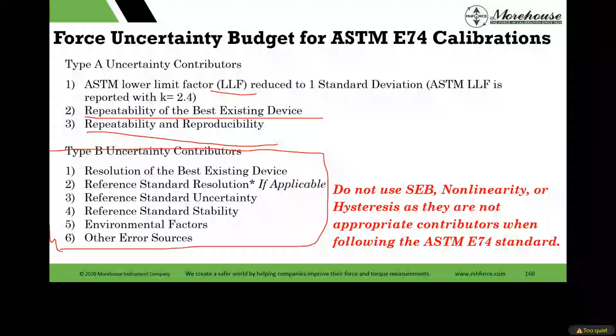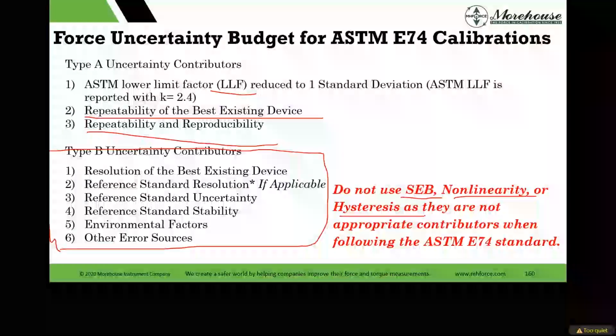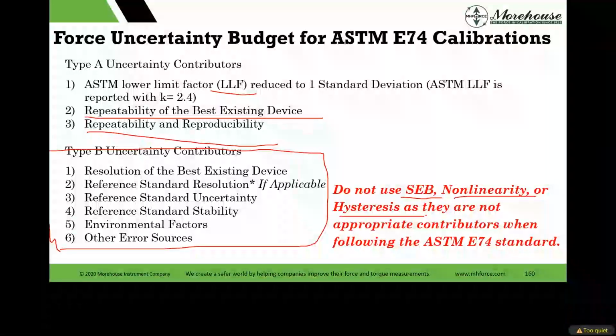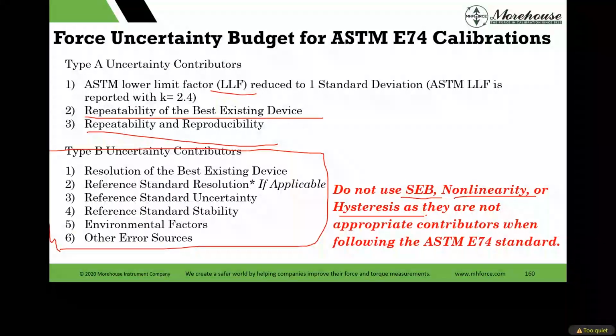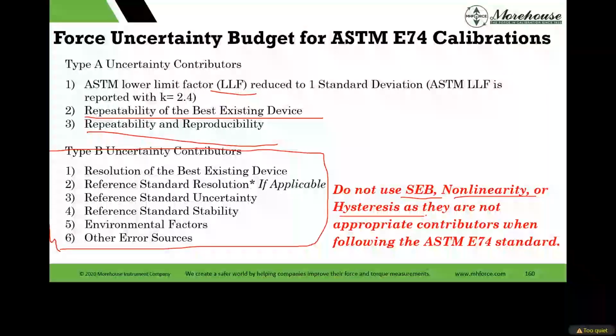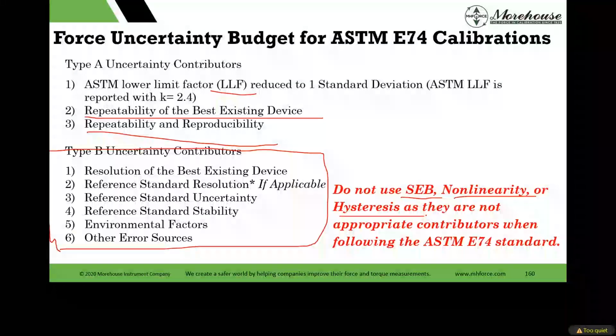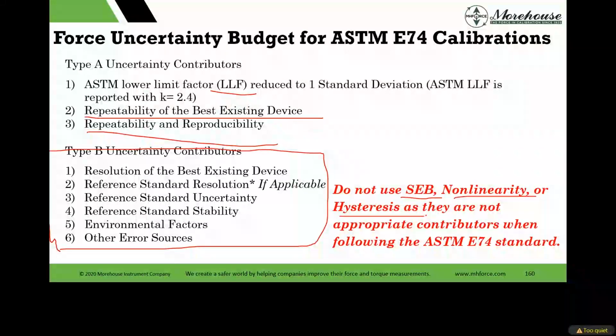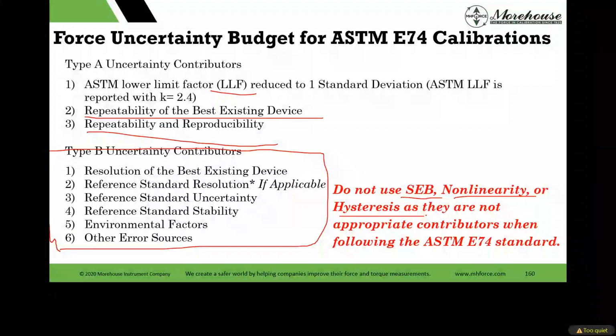What we see people mistakenly do is go back to that spec sheet. And I would say if you have an E74 calibration, these terms are virtually nice to know. They're worthless to you. You'll never use them. You're going to use that curve fit, what it should read. You're going to use those numbers in the coefficients. So I don't care about SEB. I don't care about nonlinearity. I've corrected all that. The lower limit factor, the statistical estimate of errors, has incorporated it. As long as I use that polynomial, I'm good. And I need to use a polynomial for descending measurements.